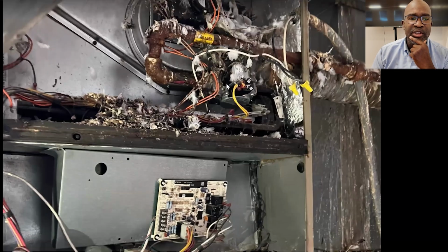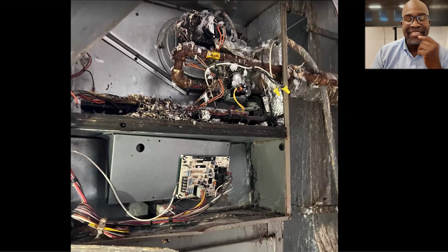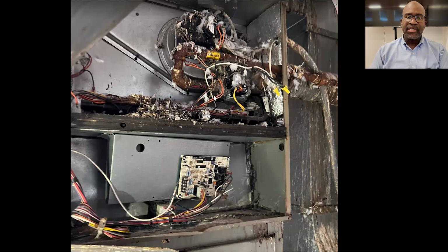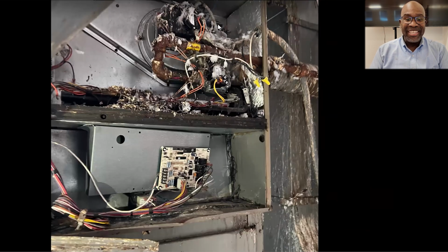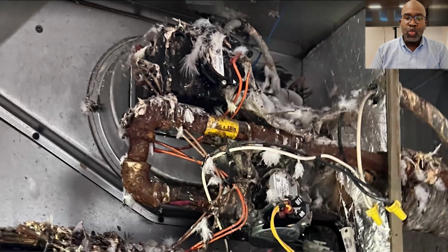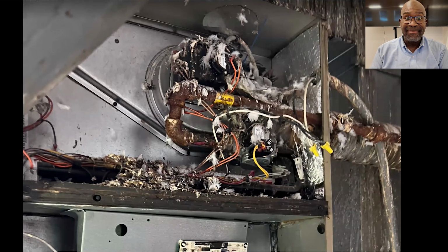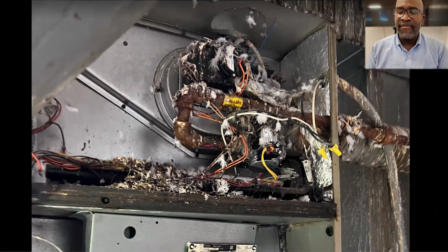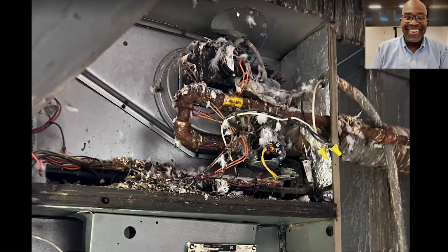When we came outside, we came across this — I removed the cover to get inside, and you can see all these feathers and things. A furnace has a combustion air fan for a couple of reasons: you don't want gas to build up and possibly explode, so it has to purge, and you also need combustion air to burn the gas. The fan was inside the furnace, and because this is outdoors, birds and mice would come into this section to try to get warm, and they'd get sucked into the combustion air fan. So what we're looking at here are bird guts — this is an eviscerated bird, and you can see the hole where the flue gases vent. The bird crawled in, got sucked into the combustion air fan, and got ripped to shreds. This is a gas line — none of this is legal, by the way. This is all completely illegal.